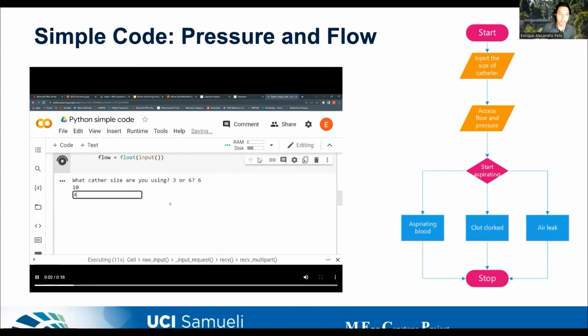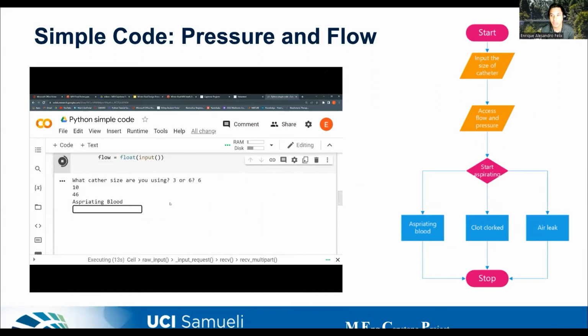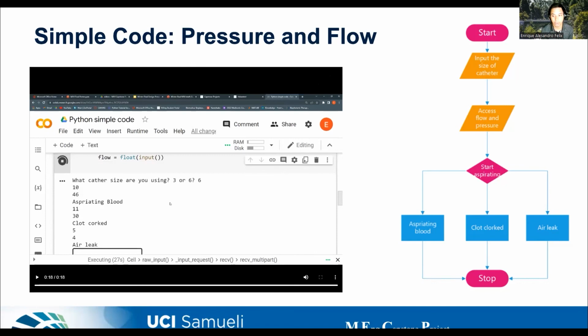Here we have our simple code that's used for the algorithm. So you first start by choosing the catheter size that you want. Then you access the flow and pressure data. This data is actually user inputted, as you can tell in the code. And then you begin your aspiration. Then you get told between aspirating blood, a clot cork, or an air leak, as you can tell from the video. From there, the physician will know what to do. We chose these three conditions due to being the most common ones that a physician might see during a thrombectomy.